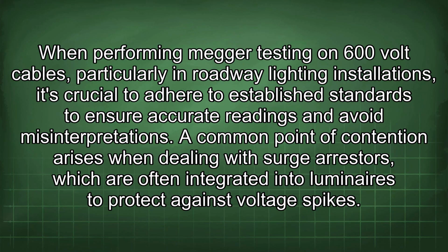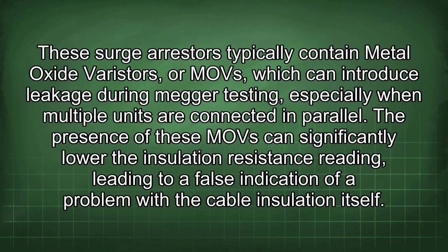When performing Megger testing on 600-volt cables, particularly in roadway lighting installations, it's crucial to adhere to established standards to ensure accurate readings and avoid misinterpretations. A common point of contention arises when dealing with surge arrestors, which are often integrated into luminaires to protect against voltage spikes. These surge arrestors typically contain metal oxide varistors, or MOVs, which can introduce leakage during Megger testing, especially when multiple units are connected in parallel. The presence of these MOVs can significantly lower the insulation resistance reading, leading to a false indication of a problem with the cable insulation itself.